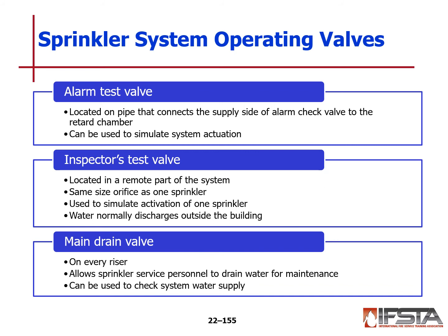With our operating valves, we may have an alarm test valve, which is located on the pipe that connects the water side of the alarm check valve to the retard chamber. This can be used to simulate the system's actuation and give us a good test.